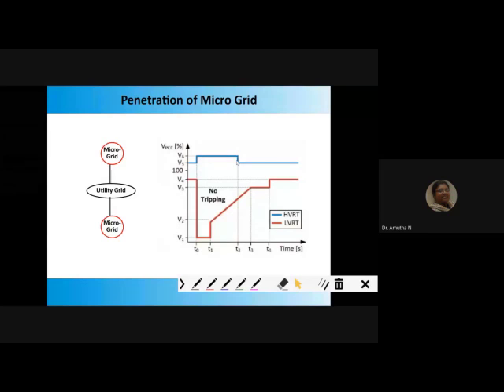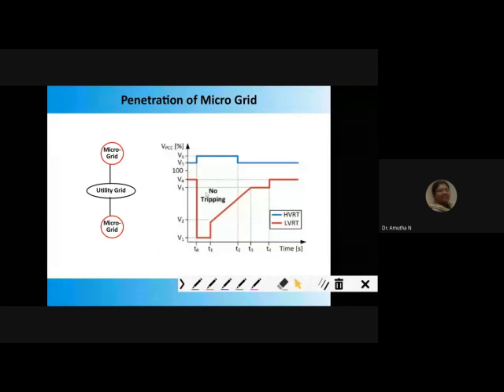Why does high voltage ride through happen? After disconnecting, auto reclosing of the relay may happen. At that time, in some cases, the voltage moves higher than the expected voltage. But in that case also, it should not be tripped off. Even if the level of high voltage is V5, it still has to remain connected.